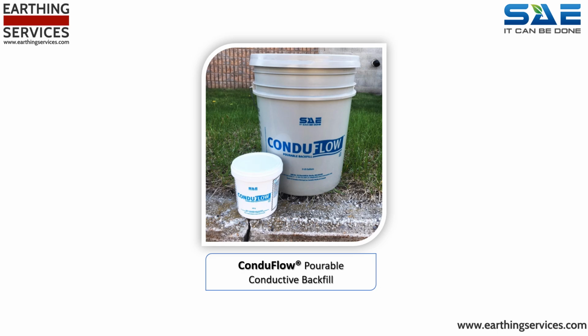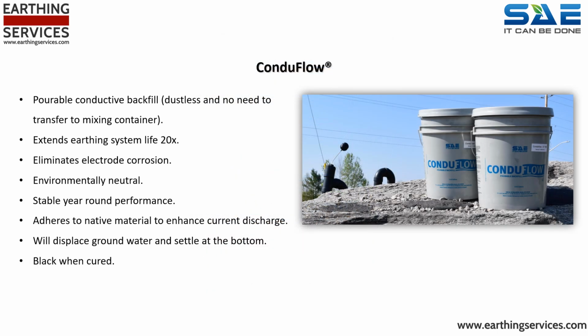We'll briefly move on to ConduFlow, which is a liquid backfill that cures over a number of hours. These are some of the specific attributes of ConduFlow, which is often installed in conjunction with ConduDiscs. These include: it is pourable, it eliminates electrode corrosion, it is environmentally neutral with stable year-round performance. ConduFlow is ideal for a range of applications, including as an earth enhancement material in difficult or corrosive environments, for transmission structures, pad mount transformers, substations, retrofit of existing earthing systems. This product is supplied in two parts, being the main conductive element and a curing agent, which solidifies the ConduFlow over a number of hours.